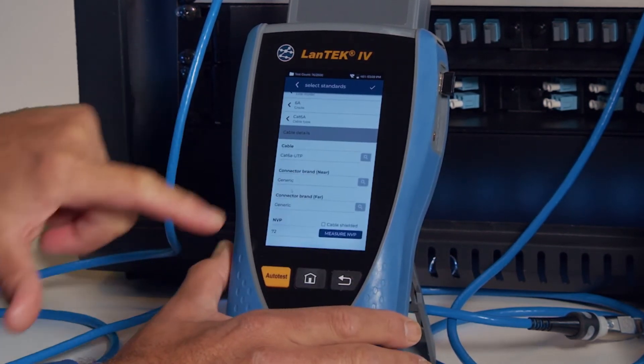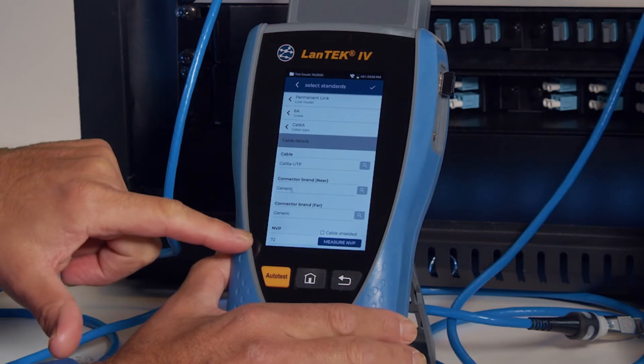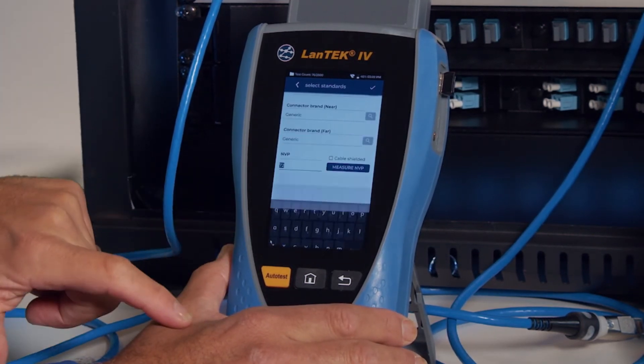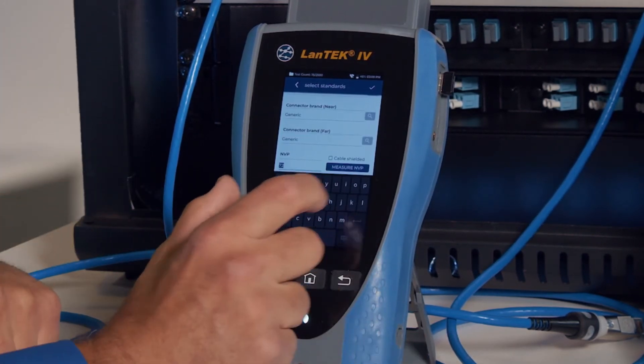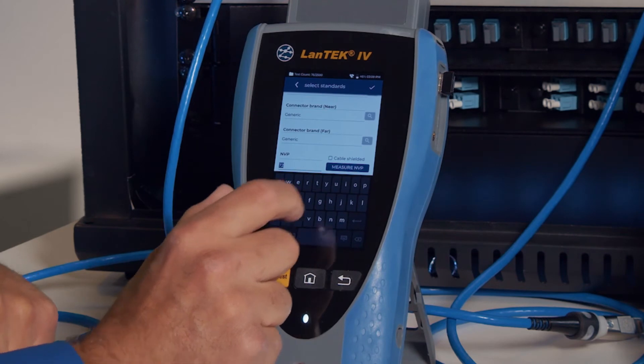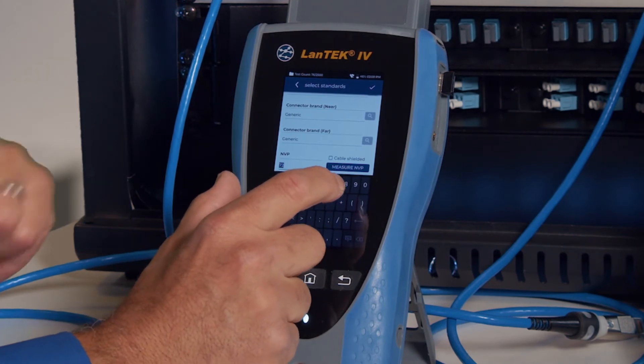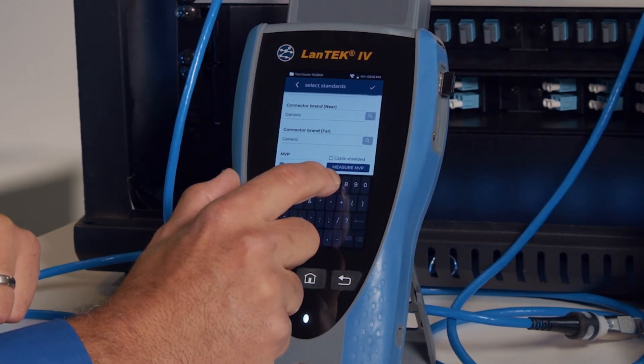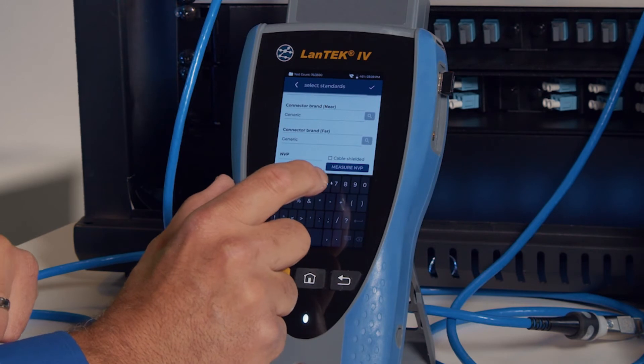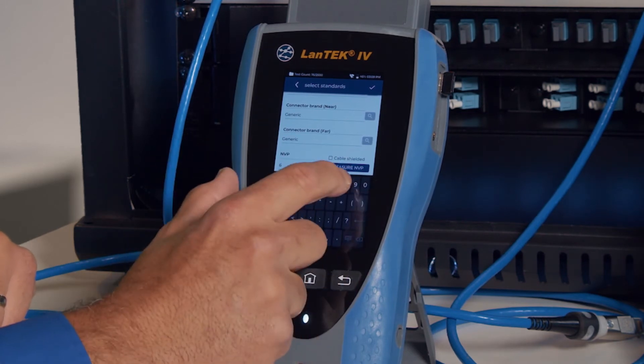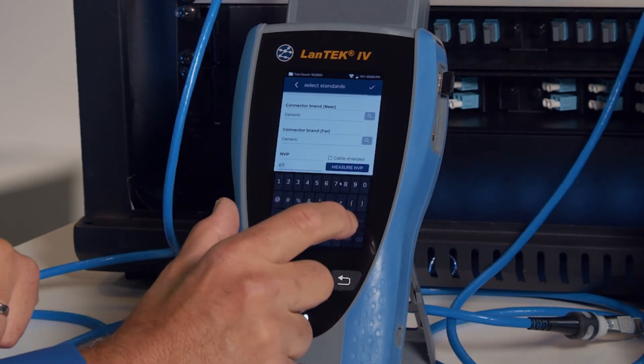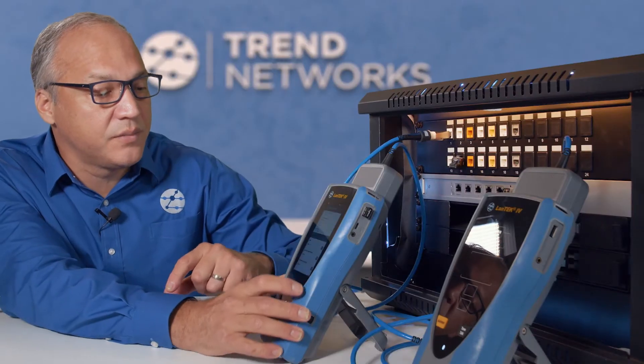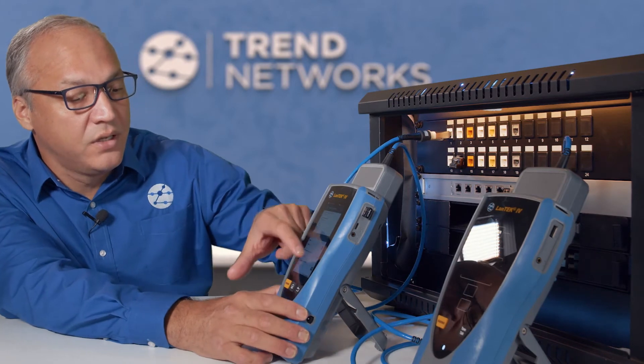The default NVP is 72. Maybe most of the cabling you install has an NVP of 68 instead of 72. Our default is 72 — we'll change that to 68. Enter. Okay.